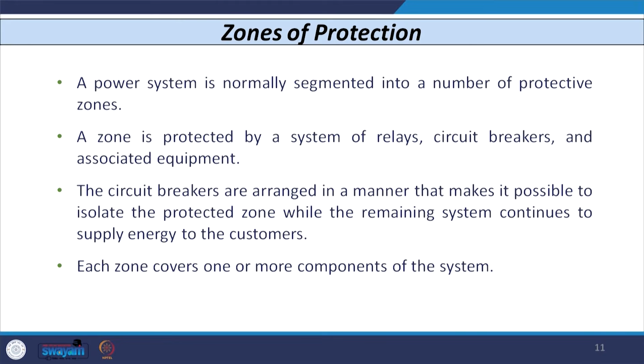So, we have to install a particular protective device for each and every equipment, and we have to design a specific zone. So, what do you mean by zone? Zone means nothing but a particular area or region in which, if any fault occurs, that protective device is capable of taking care of it. A zone is usually protected by relays, circuit breakers and other associated equipment like current transformers, potential transformers and so on. These circuit breakers are arranged in a number of different manners, so that all the devices we have discussed in the earlier slide are protected against all types of fault.